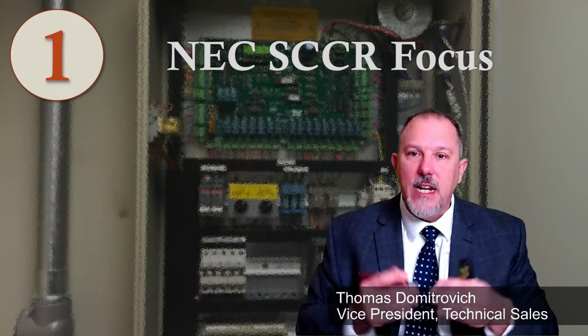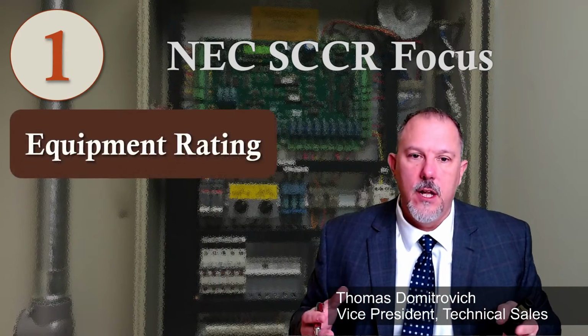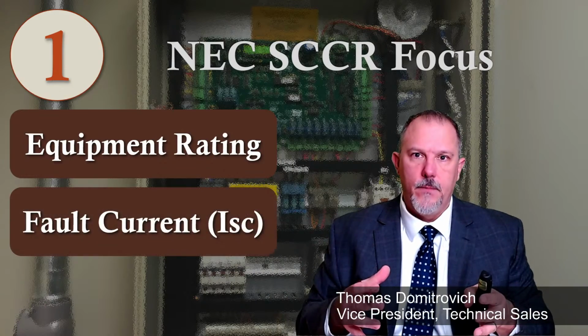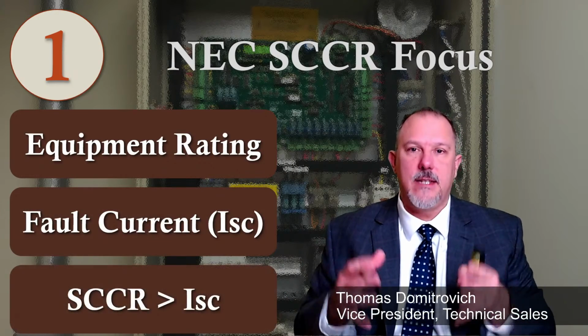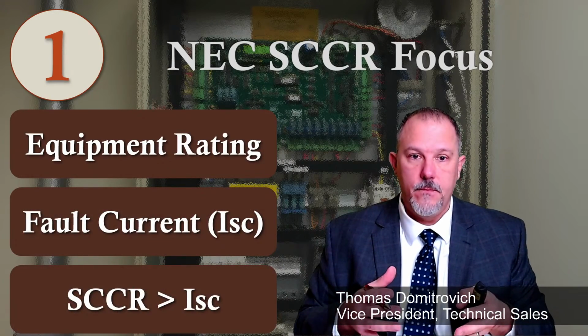It's rated for 5,000 amps. We put 65,000 amps through it. This starter is not rated for the amount of current that we're passing through it. So what happens is that the rate of change of that short circuit current puts a lot of pressure on the equipment itself, and it can't hold it together.